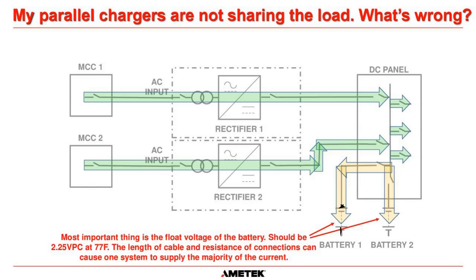That's what matters. Let's say this battery here needs exactly 135 volts DC to be charged correctly. So what you would do is put your Fluke on the battery terminals, not the charger output terminals. You wouldn't measure here. You would do it at the battery terminals. Then I would open charger 1 and adjust charger 2 until the voltage at our battery terminals is 135 volts DC.